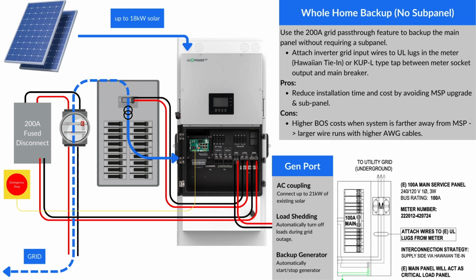From the meter, the wires will go to a 200 amp fuse disconnect, and then to the grid terminals in the inverter, and then out from the load terminals of the inverter to the main breaker and the main service panel. If the customer has some large loads, such as central air conditioning units or EV chargers, you have the option of doing some load management by moving these loads to a 60 amp subpanel and connecting the panel to the gen port of the inverter.